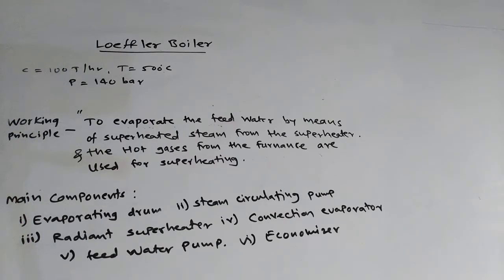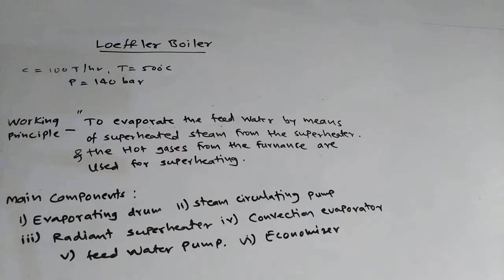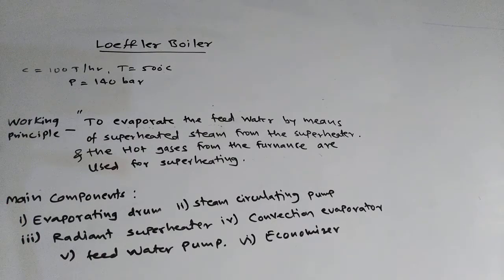The main components of the Löffler boiler are: first, the evaporating drum; then the steam circulating pump; then the radiant superheater; then the convection evaporator; the feed water pump; and finally the economizer. The evaporating drum is where the mixture of heated water and superheated steam is collected. The steam circulating pump circulates the steam. The radiant and convection superheaters are located in the combustion chamber. The feed water pump is used for pumping the feed water, and the economizer is a pre-heating device.